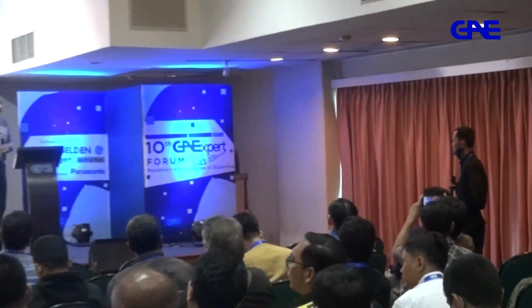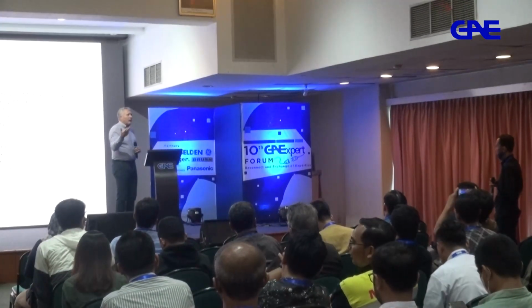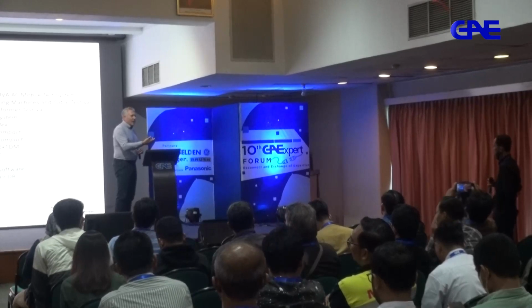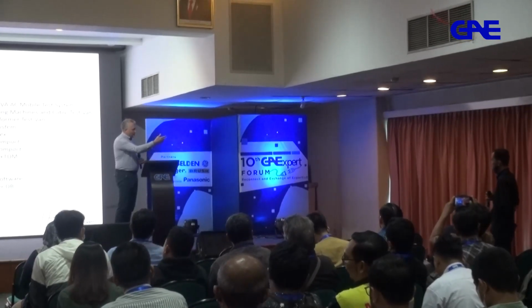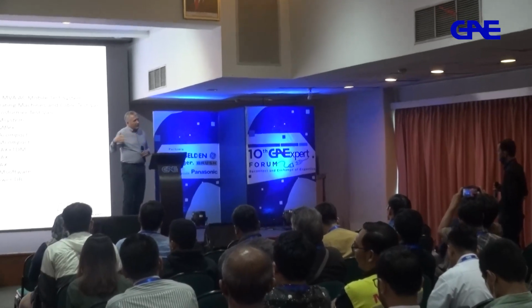Yes. So what you're measuring is, let's say, the same as putting a voltmeter and looking at how many, let's say, dB microvolts you have. This, I will say, is the first step. The next step is to get to the PRPD diagram to say what's the problem. So if you just want to, let's say, use, we manufactured those too in MEGGER, a handheld scanner to say I have PD inside of this cabinet, I would say this is just the first step of a bigger diagnosis.